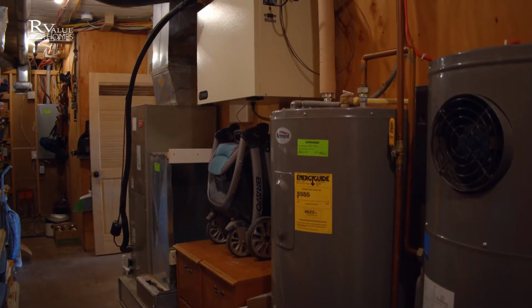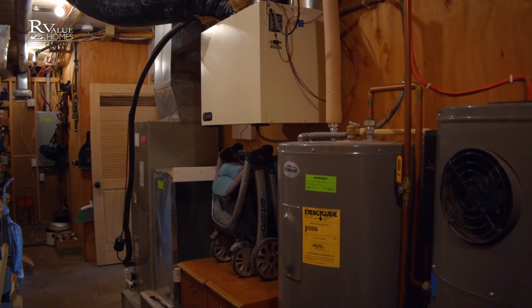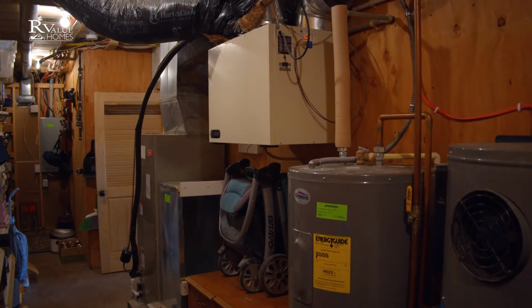We supply fresh air to a plenum room, which is typically the mechanical room, and use a grill to deliver that fresh air throughout the home, rather than tying it in with a supply ducting. That usually requires a furnace fan to run. We use a MERV 13 air filter, and it runs constantly for better air mixing.